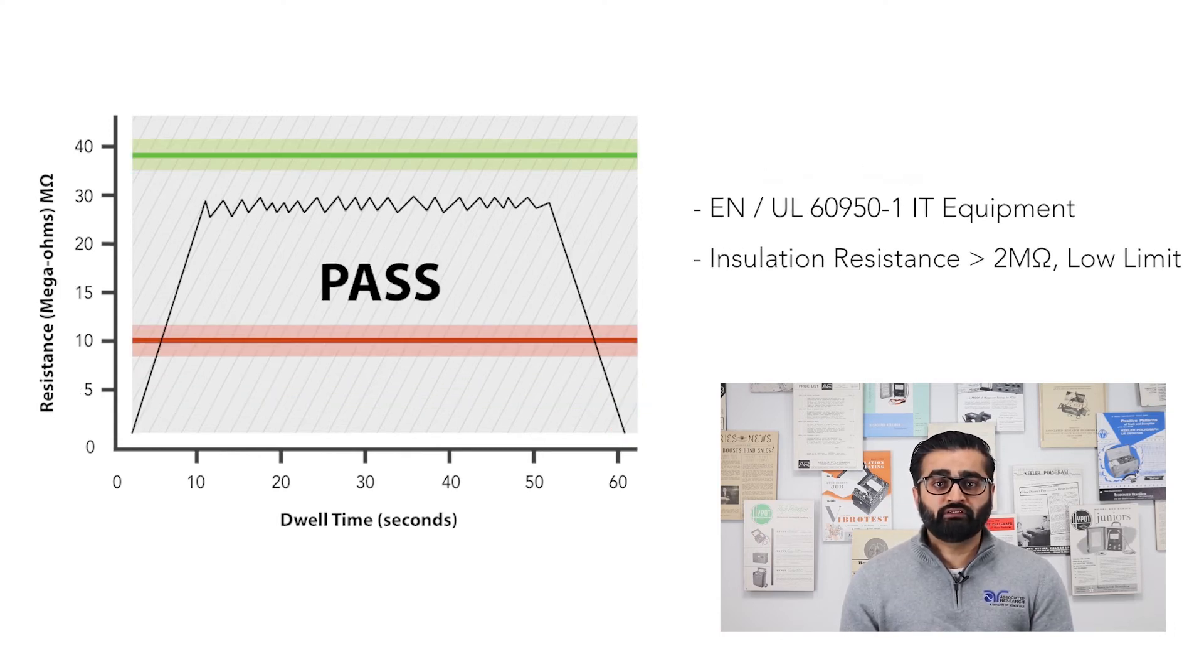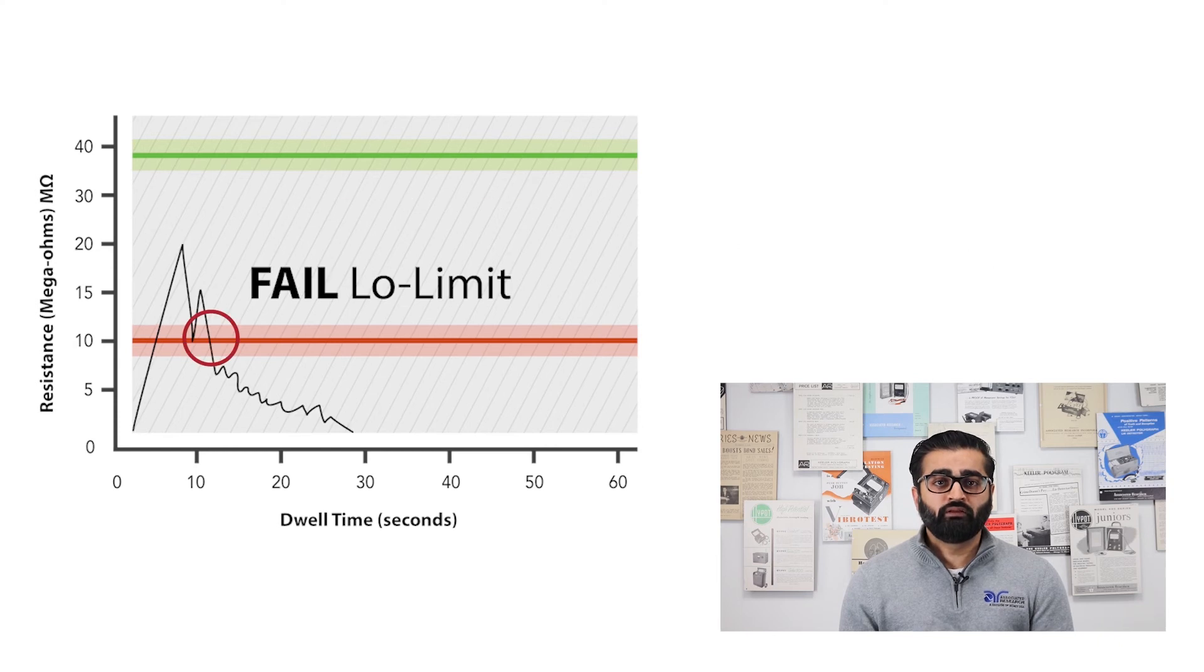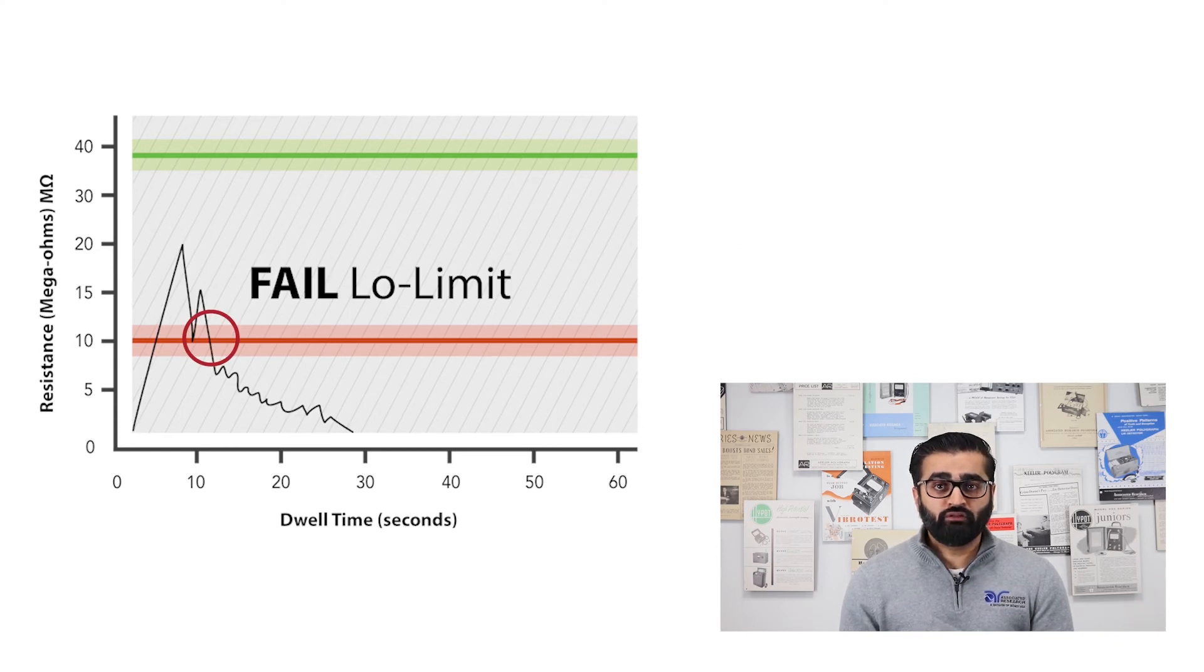Next, let's take a look at insulation resistance test. UL60950-1 IT equipment standard requires that the insulation resistance value be at a minimum 2 megaohms. Since we are given a minimum value to meet, the low limit parameter becomes a gauge for passing or failing a test. The IR value must exceed a minimum value in order to consider a pass. If an IR value falls below this low limit during the test, the test equipment will display a low limit failure, and this is considered to have failed the insulation resistance test.